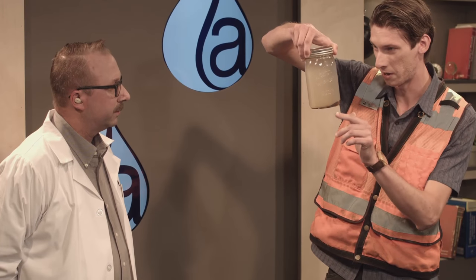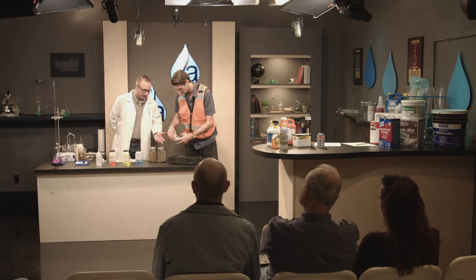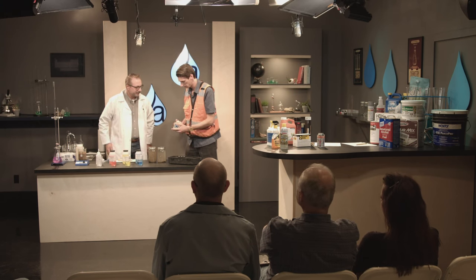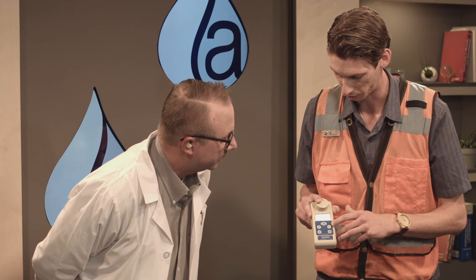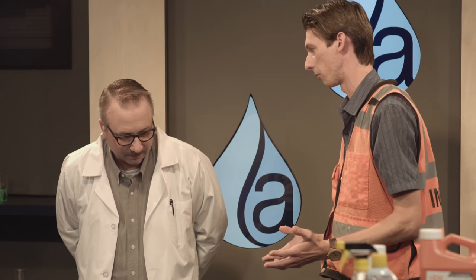You also don't want to let it sit too long — you can see all the sediment on the bottom. You have suspended solids, and we're measuring the light passing through this. It has a similar setup to the pH pen — just a calibration mode. You put in one of these four standards, hit read, and it walks you through the whole process, prompting you for the next standard.